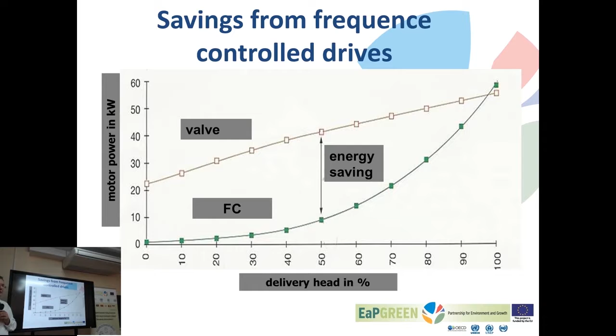This is a quite typical situation. Whenever pumps or fans have a capacity of more than 7-8 kilowatts, we need a wider range of operating conditions. A frequency controlled drive will pay back in half a year to one year easily, and they are available now also for quite big motor sizes.